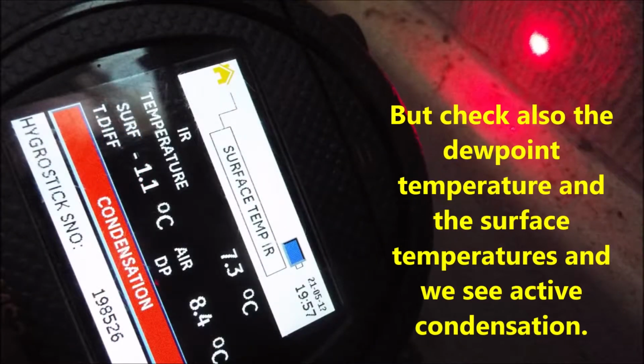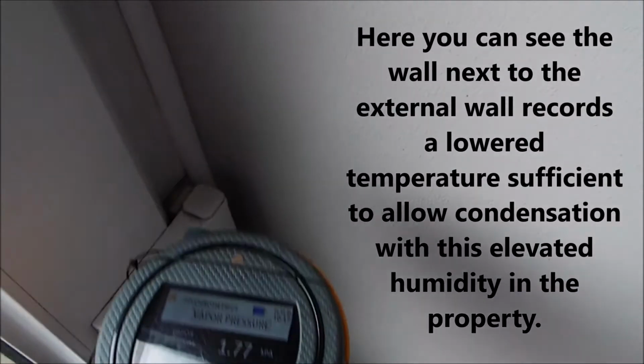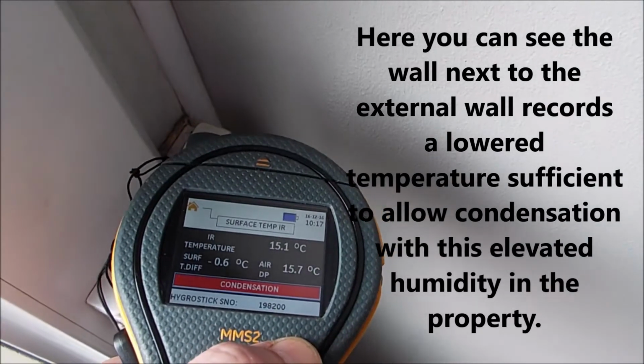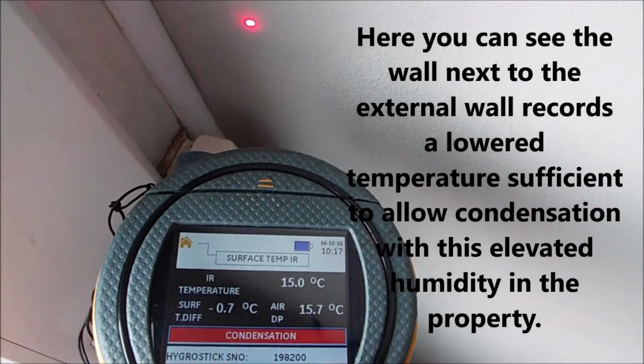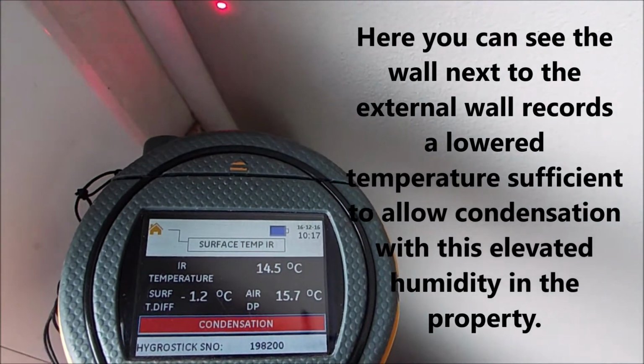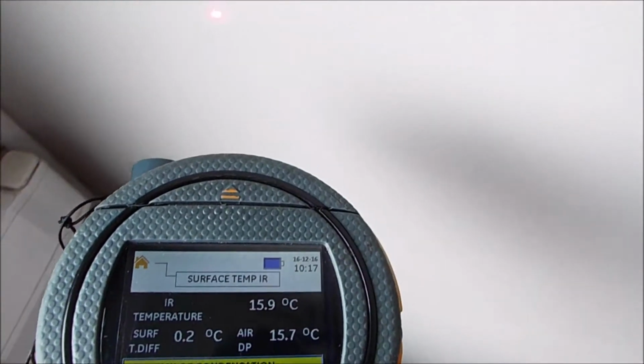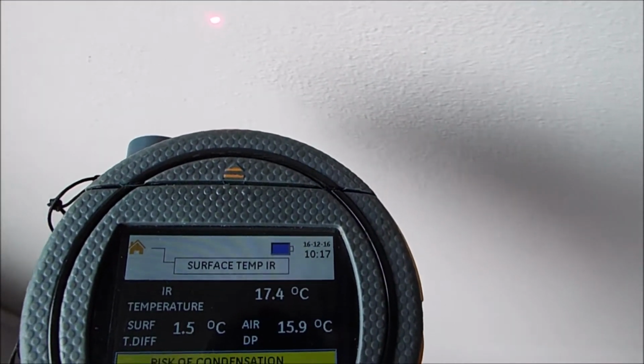Lastly, we can also check the dew point temperature of the room, whilst also measuring the temperature of the affected surfaces, and then we can see how the surface temperature has fallen below the dew point, in some areas allowing condensation to form. Now, if this condensation is regular enough, then mould growth can develop.